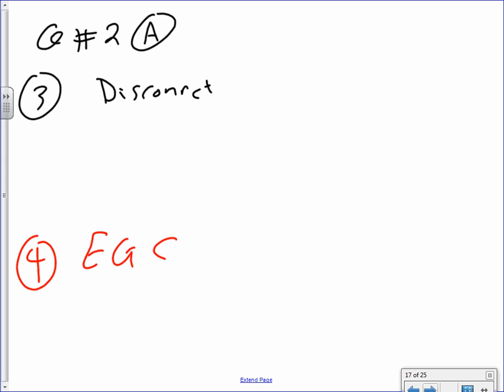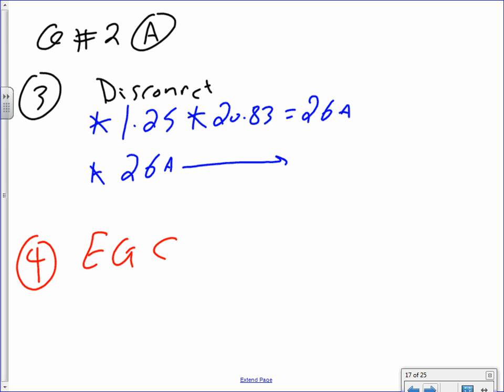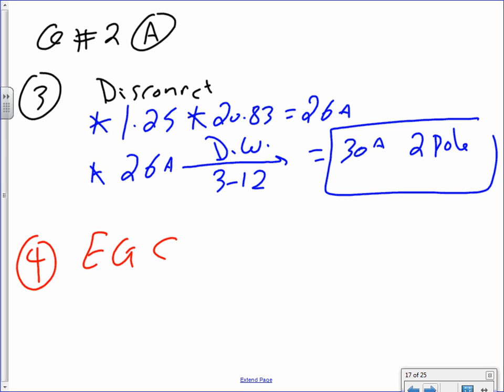For the disconnect, guys, the way I size the disconnect for this equipment, since it's a continuous load, I go 1.25, I don't have a reference for that, multiplied by 20.83, and that will give me 26 amps. And 26 amps, take it to 3-12, that will get you a 30 amp 2-pole non-fused disconnect. So I treat it like a continuous load sizing.